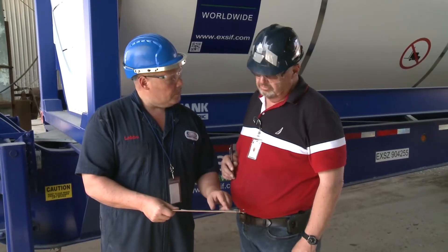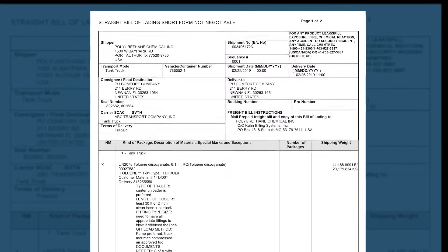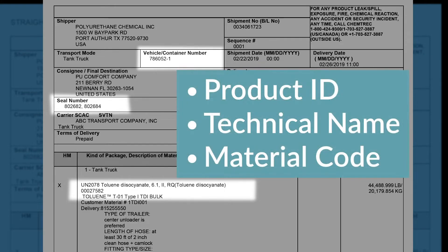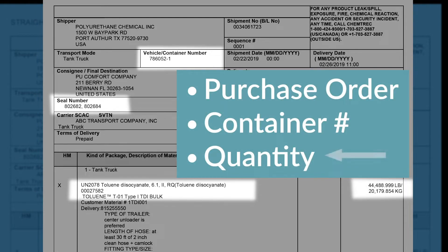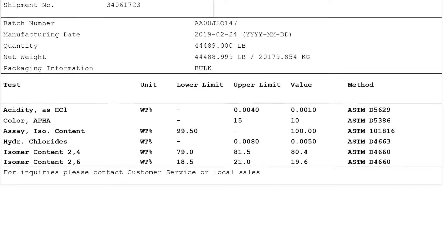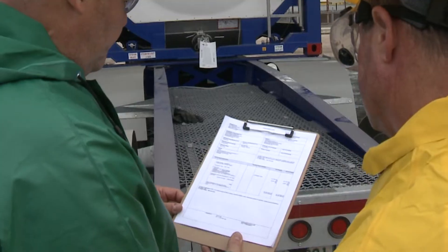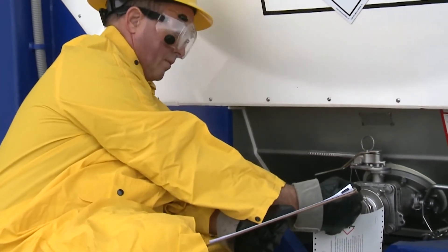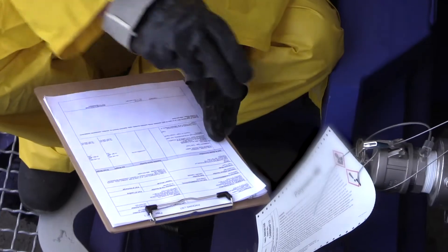Check all paperwork for accuracy. Verify the driver's paperwork to validate trailer number, product identification tag, and security seals. Confirm that the material being received is the correct TDI product, and that the weigh ticket shows the quantity being delivered to help ensure the volume of the delivery will fit the storage tank. Review the values on the certificate of analysis to determine whether the product meets required specifications. Once all paperwork is verified, check the tank container to make sure the numbers on the security seals match the seal numbers shown on the paperwork.